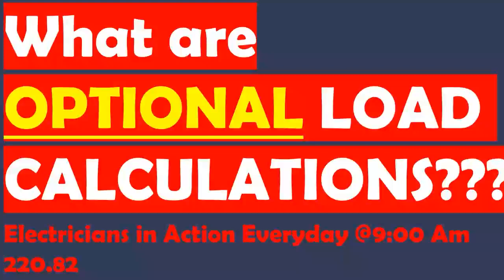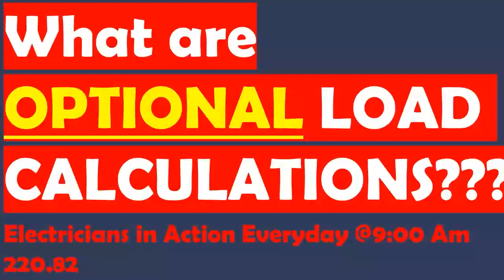When we're dealing with optional calculations — multifamily, optional calculations for schools, restaurants, whatever — we're going to be applying a specific set of rules that differ greatly from those in the standard load calculations. For example, in the standard load calculation you're going to use the range table of 220.55, the dryer table of 220.54, and you're going to do the 75% for four or more. All of those things are in what we call the standard method, and they all disappear when we get to the optional method.